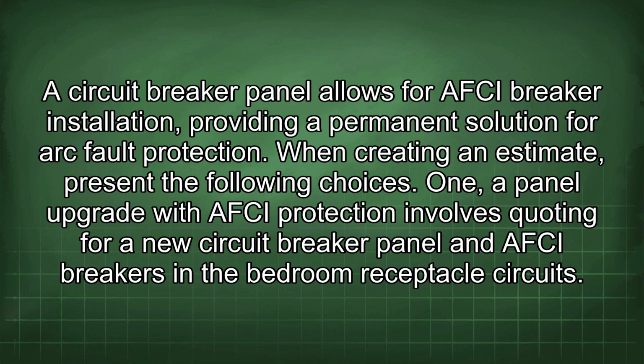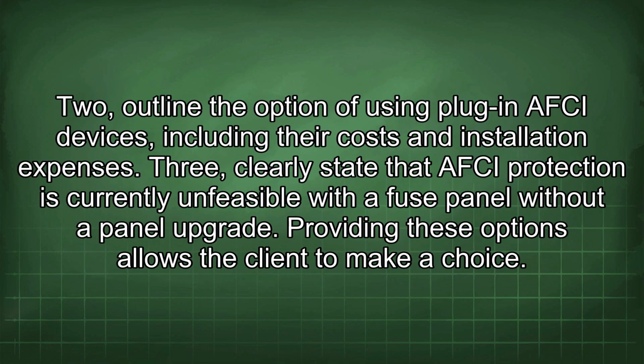When creating an estimate, present the following choices. 1. A panel upgrade with AFCI protection involves quoting for a new circuit breaker panel and AFCI breakers in the bedroom receptacle circuits. 2. Outline the option of using plug-in AFCI devices, including their costs and installation expenses. 3. Clearly state that AFCI protection is currently unfeasible with a fuse panel without a panel upgrade. Providing these options allows the client to make a choice.